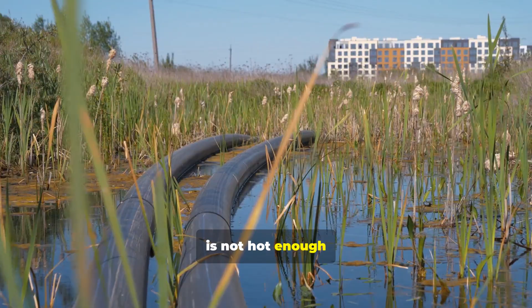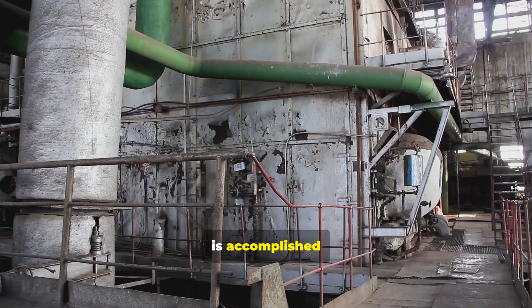These municipal networks typically require water heated to between 80 and 120 degrees Celsius, or 176 to 248 degrees Fahrenheit, to effectively warm buildings, especially during the harsh Nordic winters. The critical task is to lift the temperature of the waste heat from its low-grade state to this high-grade, usable level. This transformation is accomplished using large, industrial-scale heat pumps.